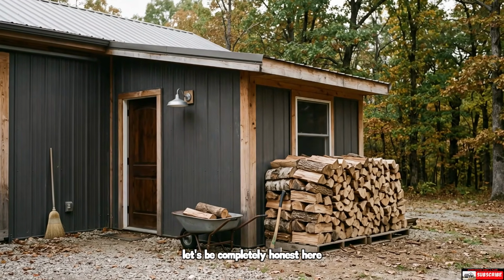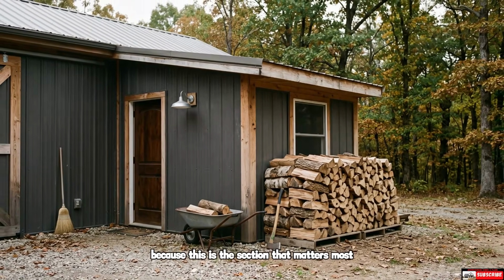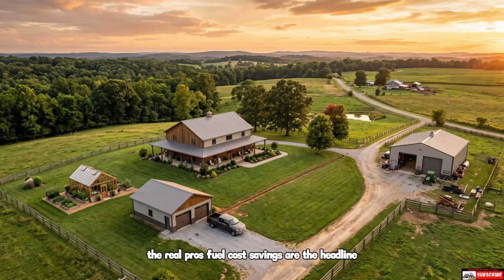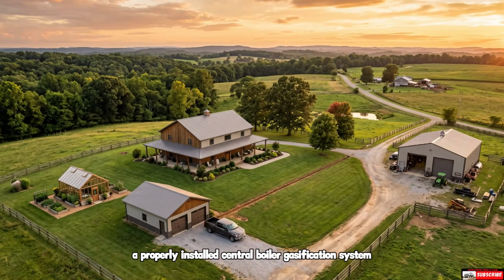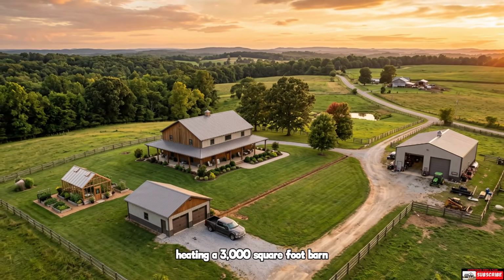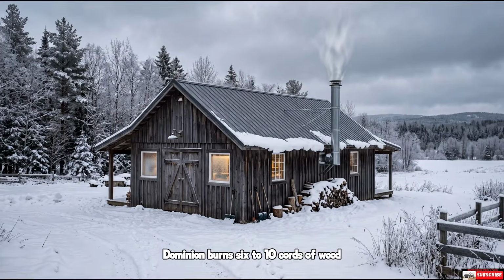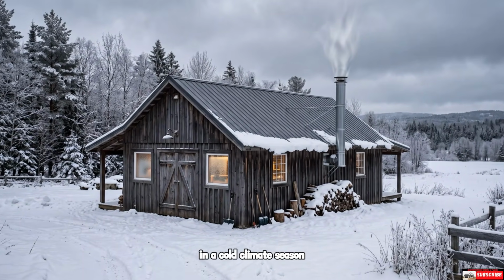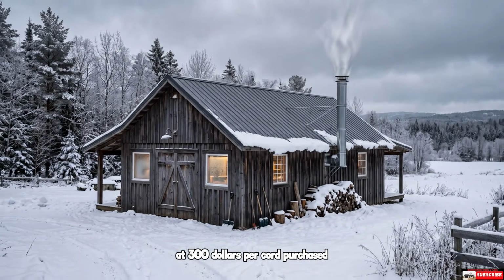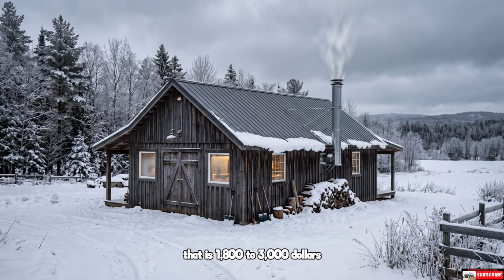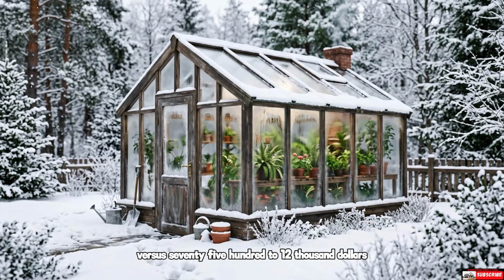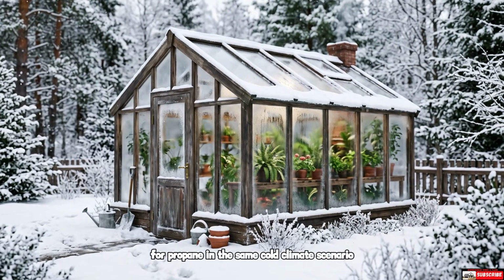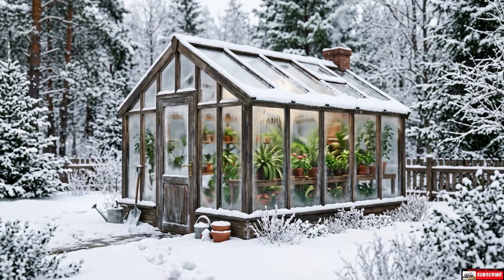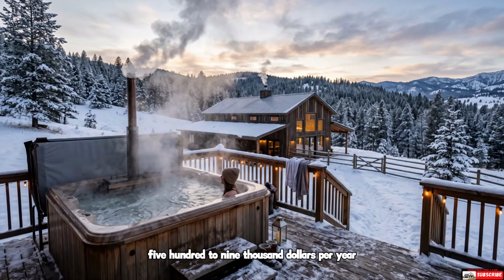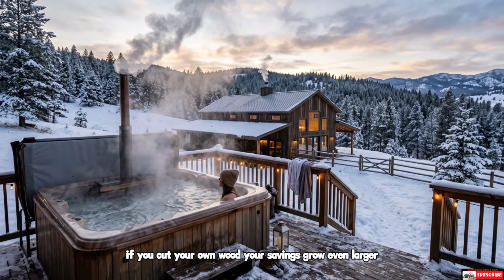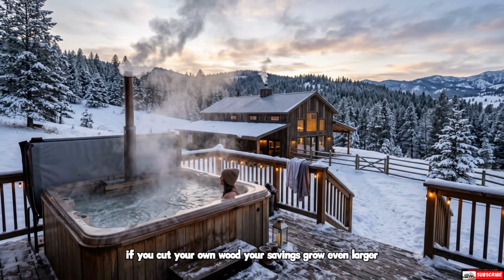Let's be completely honest here, because this is the section that matters most. The real pros: fuel cost savings are the headline. A properly installed central boiler gasification system, heating a 3,000 square foot barndominium, burns 6 to 10 cords of wood in a cold climate season. At $300 per cord purchased, that is $1,800 to $3,000, versus $7,500 to $12,000 for propane in the same cold climate scenario. Your annual savings range from $4,500 to $9,000 per year. If you cut your own wood, your savings grow even larger.